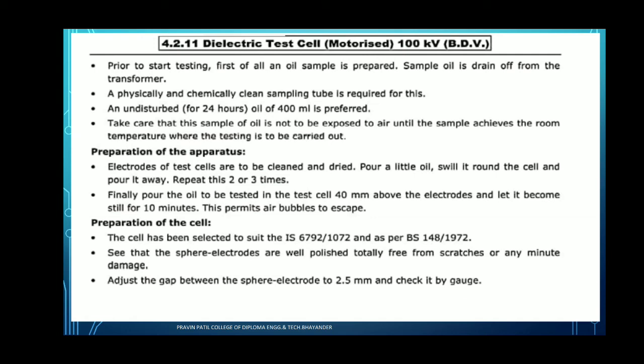So first, preparation of the apparatus. The electrodes of the test cell are to be clean and dry. Pour a little oil, swirl it around the cell, and pour it away, and then repeat this 2 to 3 times. So the procedure is repeated until the electrodes of the test cell are clean and dry. Finally, pour the oil sample into the test cell to 40 mm above the electrode and let it stand still for 10 minutes. This permits the air bubbles to escape.